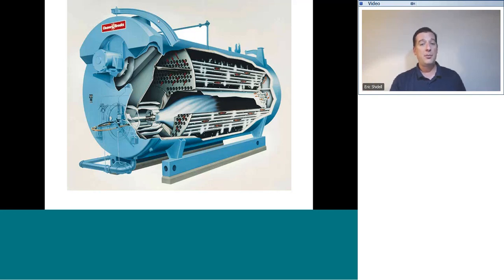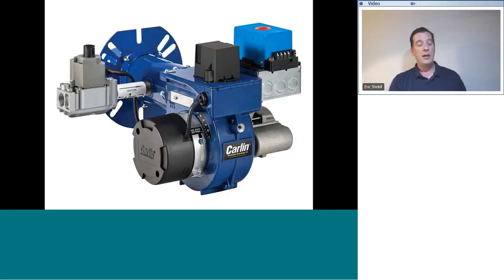Here's a shot of a small residential-style power burner. This would be used in the event that you are retrofitting an oil-burning appliance and configuring it to burn a gas fuel. We take out the standard oil burning burner and replace it with this one. That whole appliance combustion chamber is designed to operate with the forced draft system, so we have to give it a forced draft gas burner to work with too. And boom, here is a forced draft gas burner. The neat thing about this little burner is it shows how a power burner is built. So you can get it all in one picture with a small one. You can understand how much larger one goes.